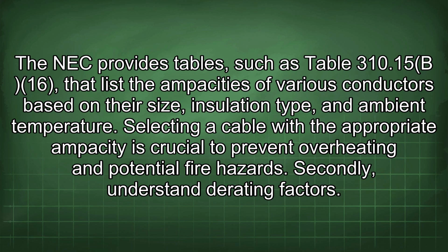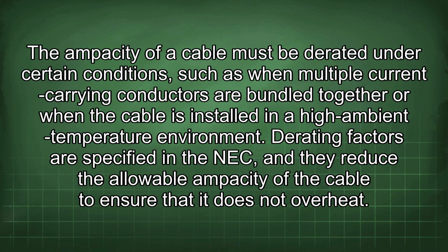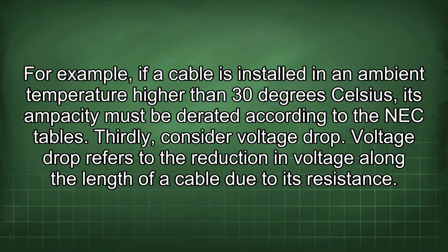Secondly, understand derating factors. The ampacity of a cable must be derated under certain conditions, such as when multiple current-carrying conductors are bundled together or when the cable is installed in a high ambient temperature environment. Derating factors are specified in the NEC, and they reduce the allowable ampacity of the cable to ensure that it does not overheat. For example, if a cable is installed in an ambient temperature higher than 30 degrees Celsius, its ampacity must be derated according to the NEC tables.